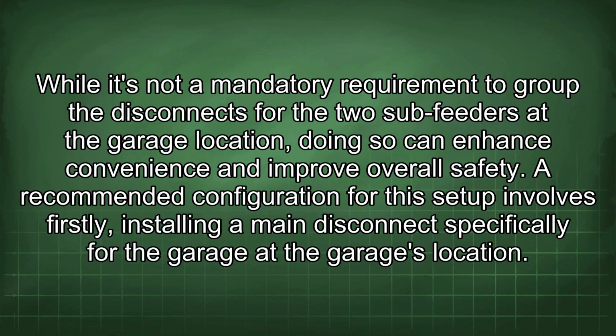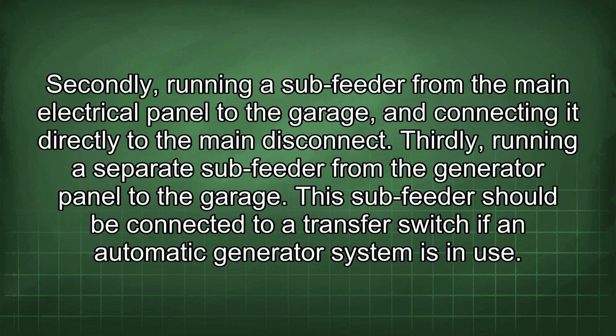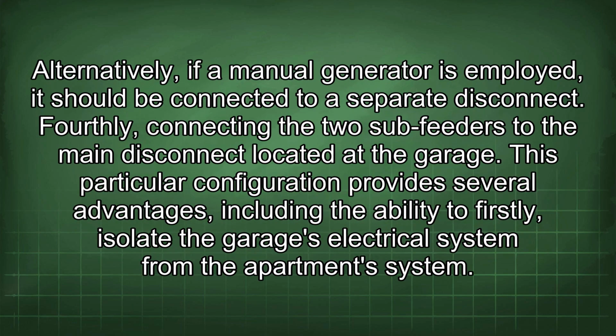A recommended configuration for this setup involves, firstly, installing a main disconnect specifically for the garage at the garage location. Secondly, running a sub-feeder from the main electrical panel to the garage and connecting it directly to the main disconnect. Thirdly, running a separate sub-feeder from the generator panel to the garage. This sub-feeder should be connected to a transfer switch if an automatic generator system is in use. Alternatively, if a manual generator is employed, it should be connected to a separate disconnect. Fourthly, connecting the two sub-feeders to the main disconnect located at the garage.